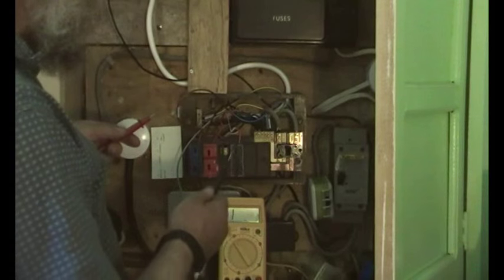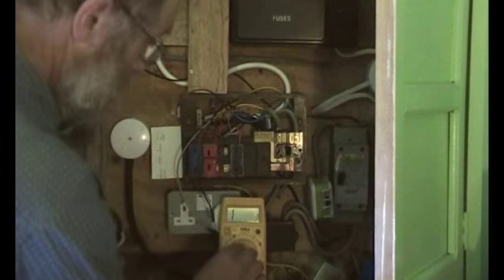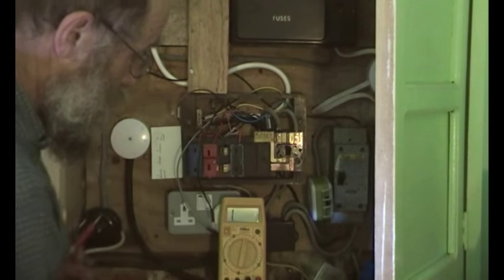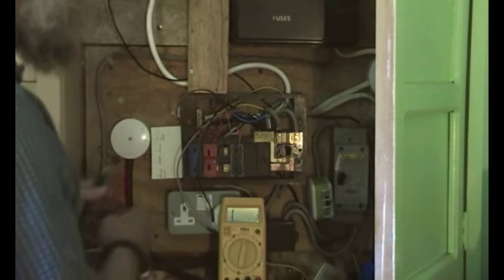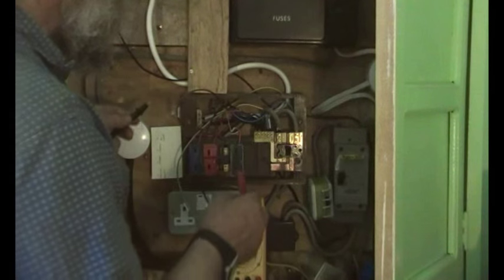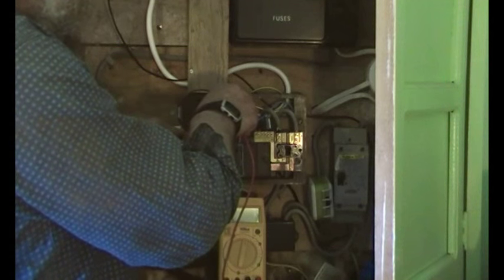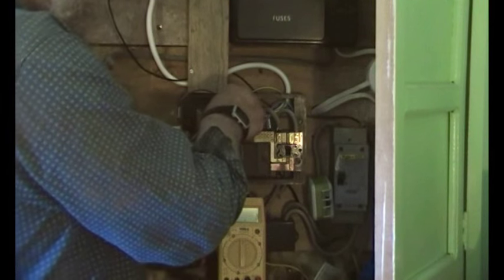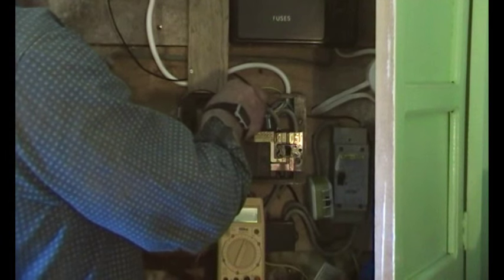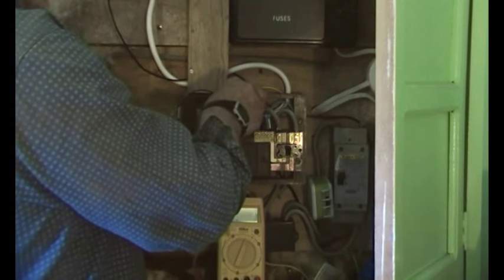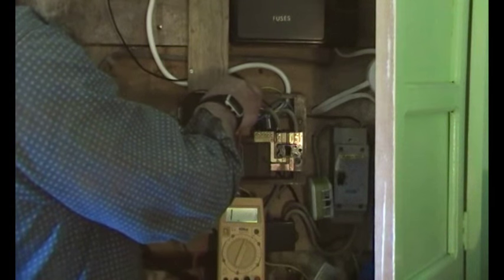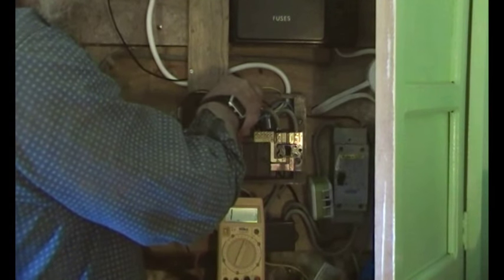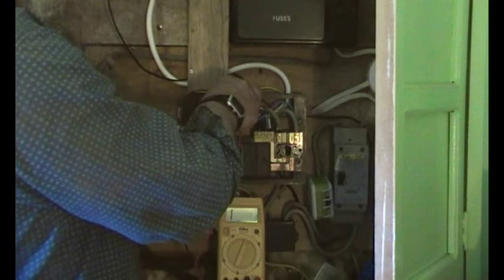And then we need to go between, we need to turn this round to 2 meg I think. See what happens. We're going between there and the earth. And there's nothing. So that's good. There's nothing between the live and the earth.